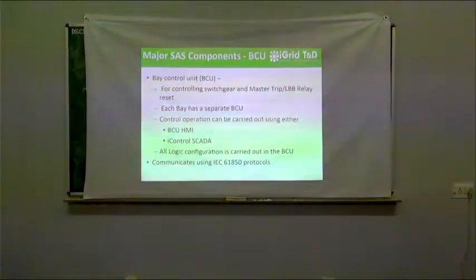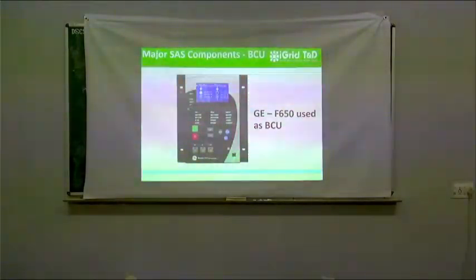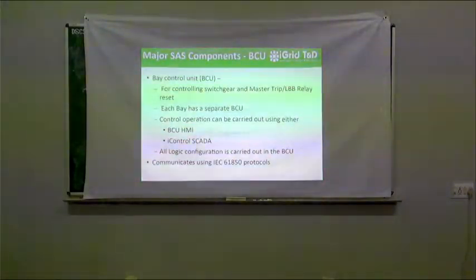The control operation can be carried out using two things. One is using the BCU HMI. So this is called the BCU HMI. Using the BCU HMI I can do the control operation, or I can also do it using the SCADA. Now, what is the reason that I require a BCU separately? Because when you see the technical specification of any substation automation, they say that you should not mix the protection activity with the control operation. So we use the BCU only for control operation.